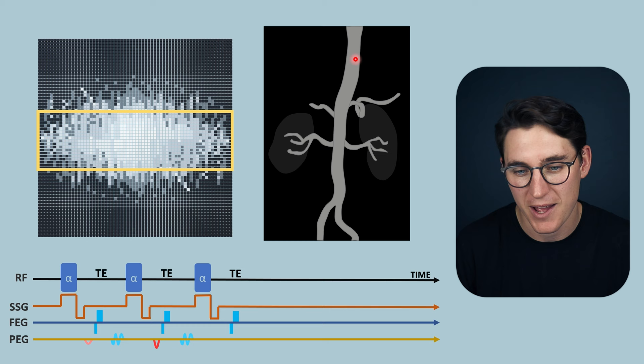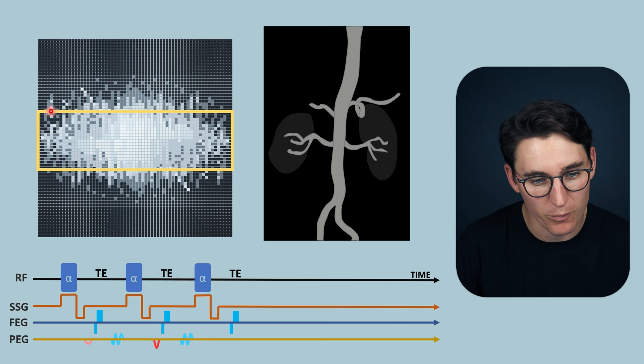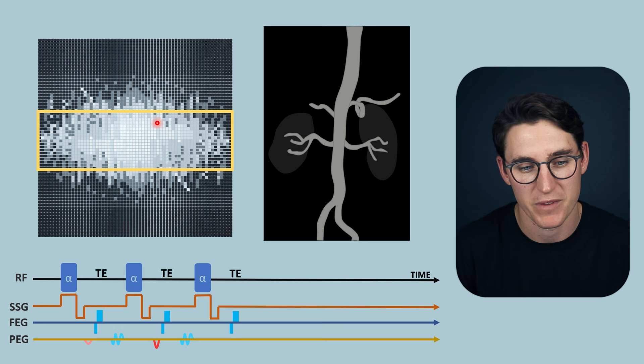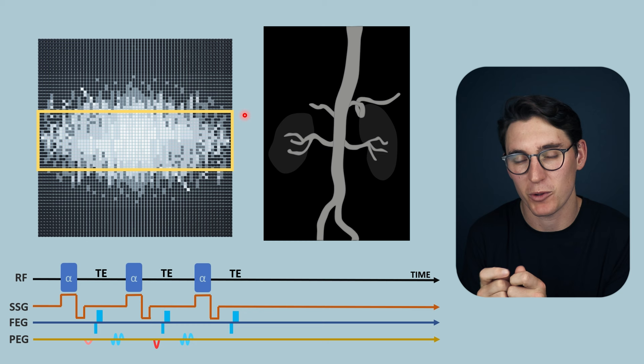Obviously, the more we try to get temporal resolution — the more rapidly we sample the center of k-space — the more we lose some spatial resolution. It's a trade-off: the more we sample the entirety of k-space, the better the spatial resolution, but we get a loss of temporal resolution.